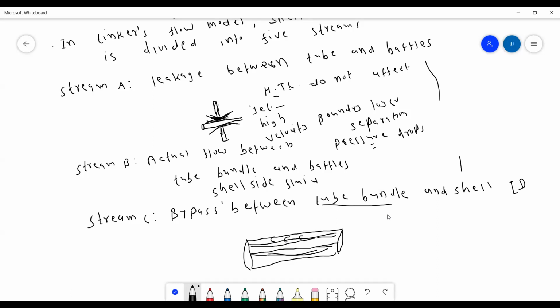This also affects the shell side heat transfer coefficient, because the fluid has to flow across the tubes for heat transfer, but in this condition fluid may bypass between tube bundle and shell ID. So in this situation, some fraction of fluid does not come in contact with tubes, which reduces the heat transfer coefficient of the shell side fluid.